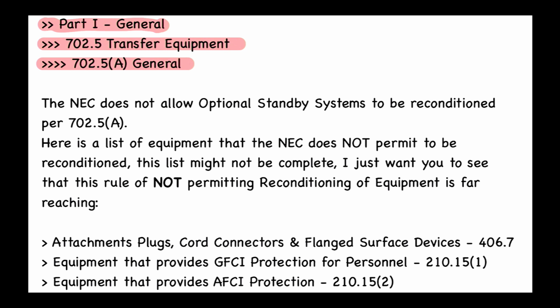It says, transfer equipment shall be required for all standby systems subject to the requirements of this article and for which an electric utility supply is either the normal or standby source. Transfer switches shall not be permitted to be reconditioned. And there's a period after that. It doesn't give you any exceptions or any other ways to do it. It just says that it shall not be permitted.